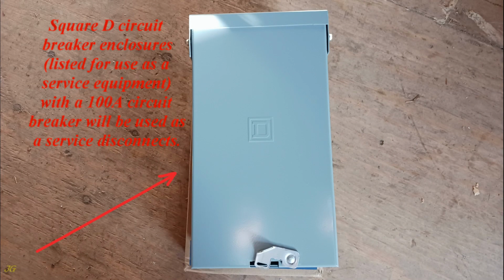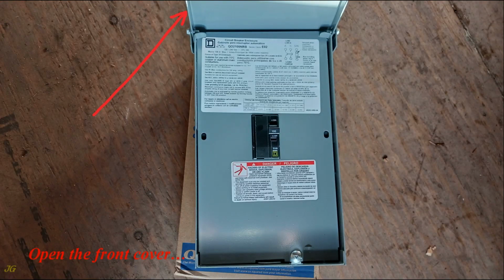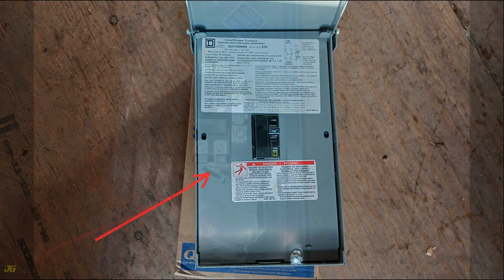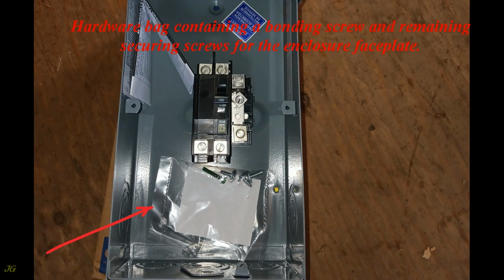Square D circuit breaker enclosures, listed for use as service equipment, with a 100 amps circuit breaker will be used as service disconnects. Open the front cover. Unscrew the screw and remove the enclosure faceplate. Hardware bag containing a bonding screw and remaining securing screws for the enclosure faceplate.